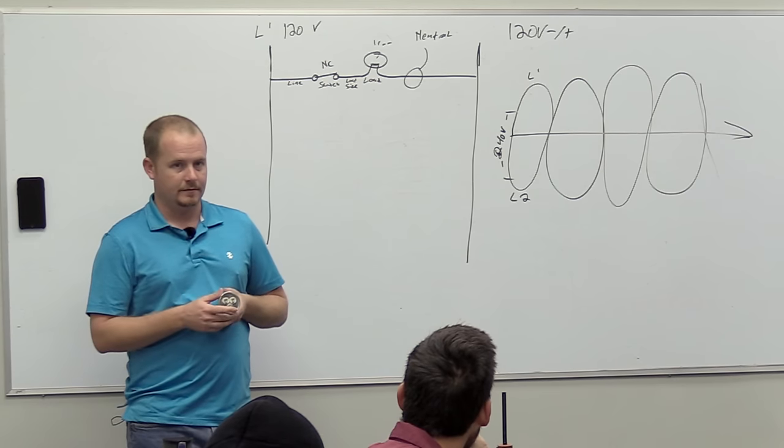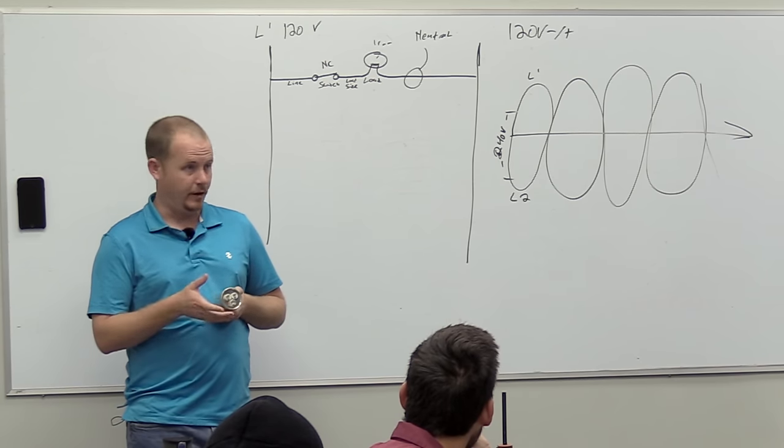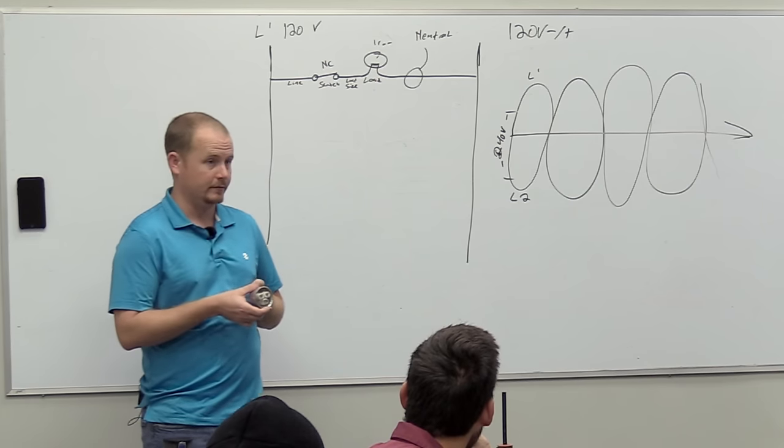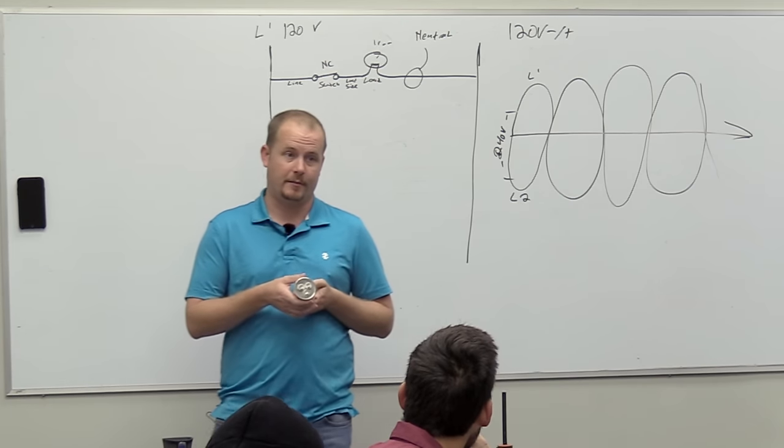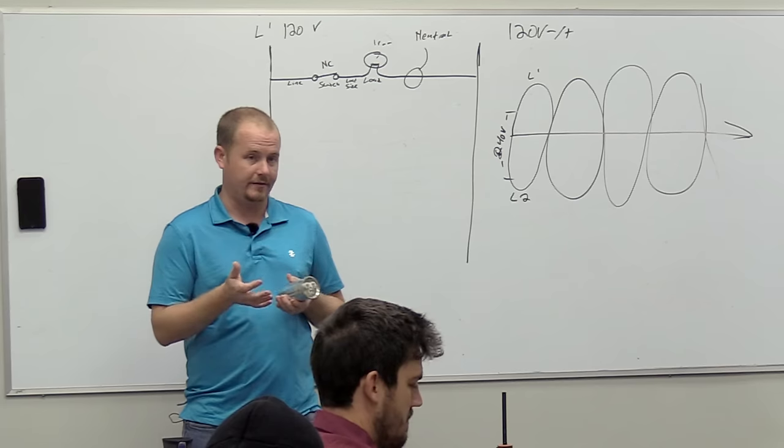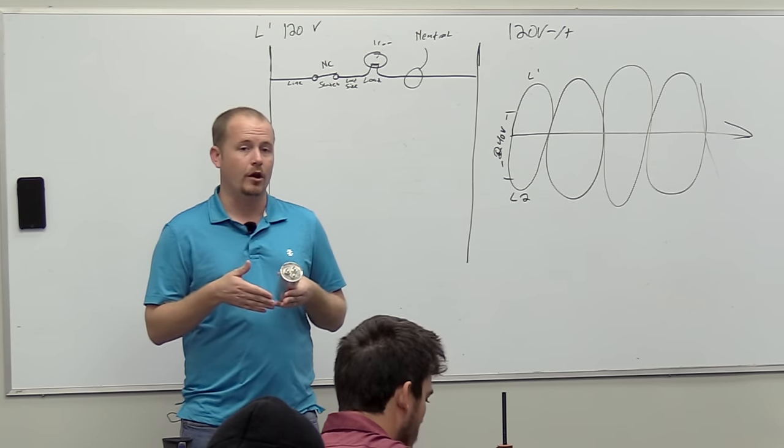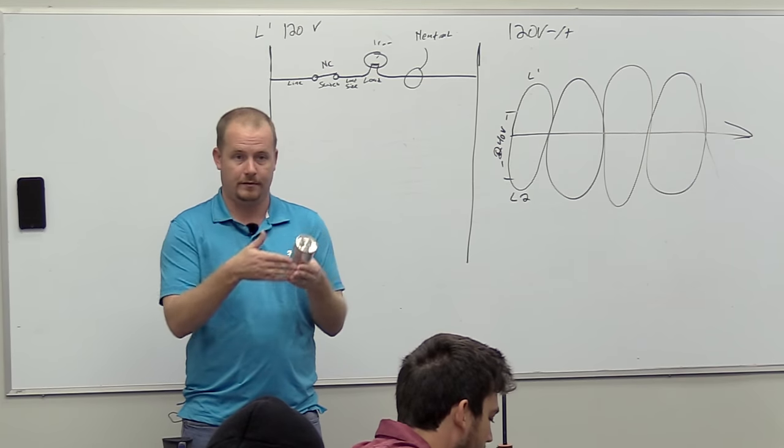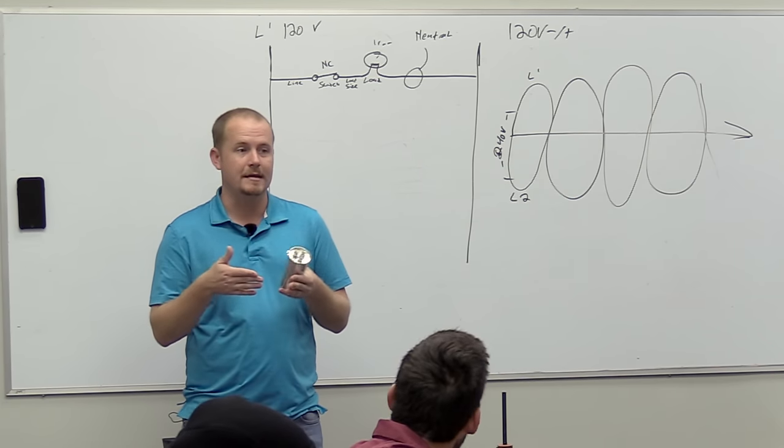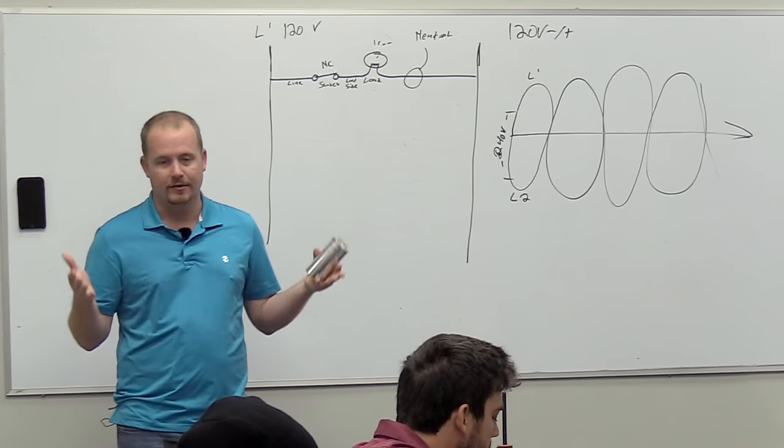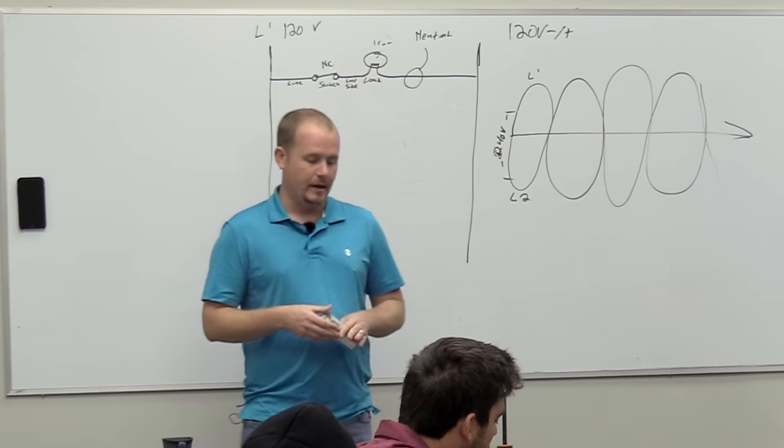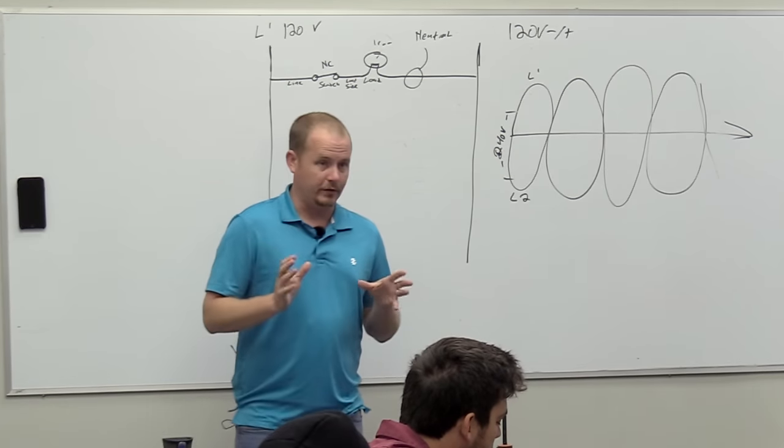Common is the separate between. Right. There's two capacitors in this capacitor. A fan cap and a compressor capacitor, a larger and a smaller. And common is the common point between the two. So when we say common in electricity, all we're saying is it's a common point. That's all it means. It doesn't mean ground. It doesn't mean the same as neutral. It just means a common point.